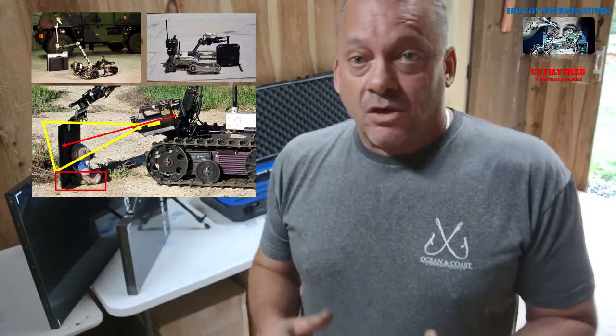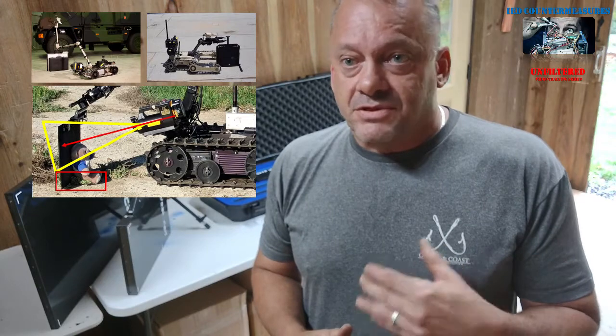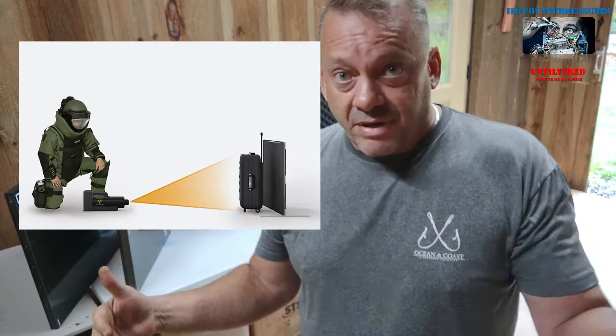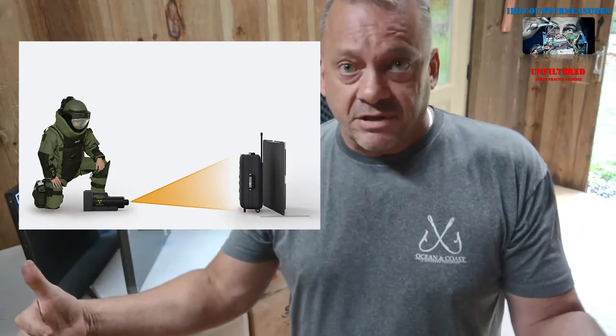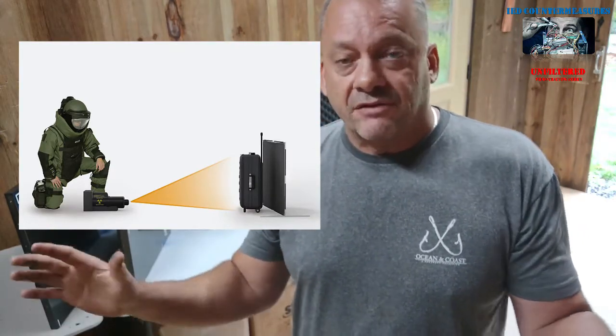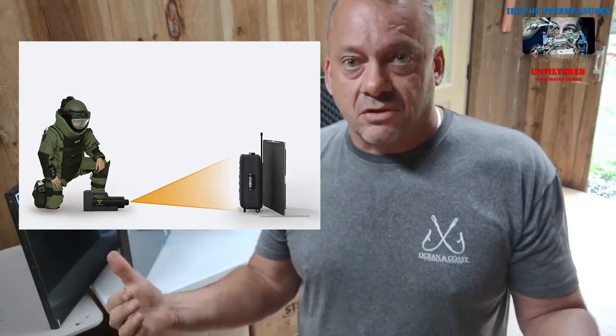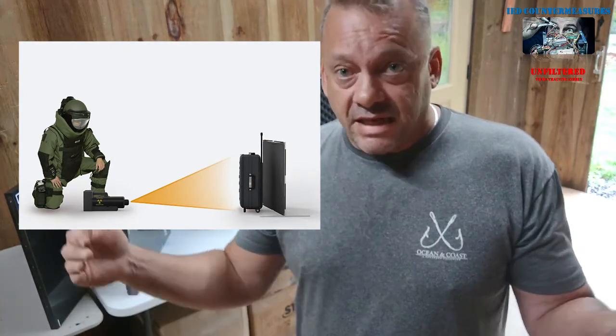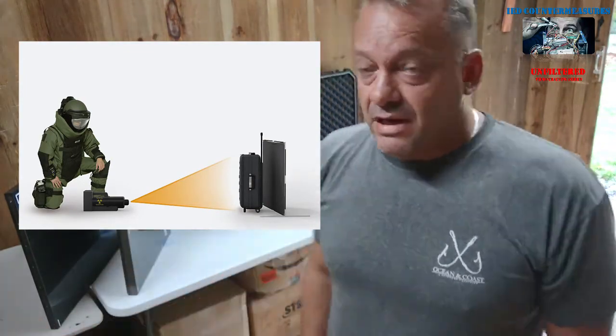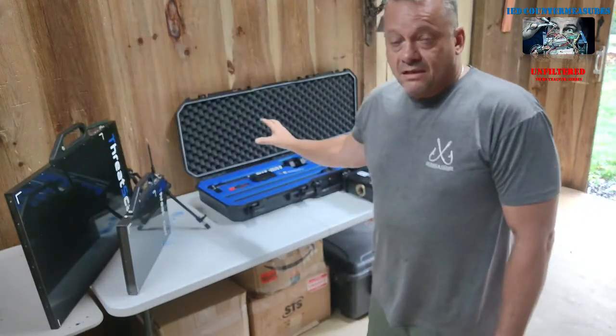So don't buy them. What you want is a C-arm. There's a lot of different C-arms out there, but you'll see a lot of failures in how they deploy them, and we'll talk about that with this system. If you're X-raying something on the ground, your panel's on the ground, your generator needs to be on the ground, period, or you're going to have a lower edge cutoff. So if you're using a C-arm for a ground scan, it needs to have both the generator and the panel on the ground. This system does that.